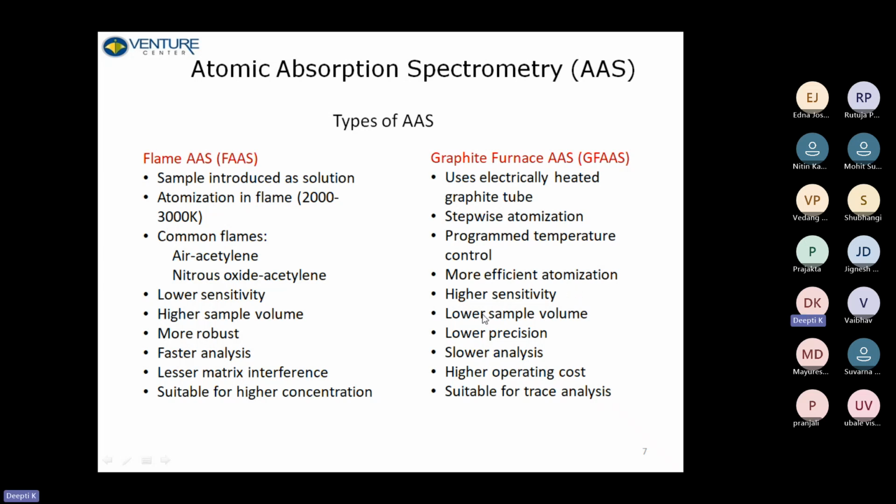The sample requirement is lower. It is usually in microliters. Precision, unfortunately, because it suffers from slightly higher matrix effects, is slightly lower as compared to flame. But it is suitable for trace analysis, performing elemental analysis in trace quantities.